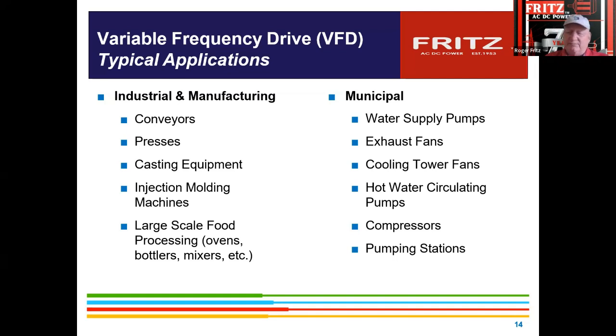We did some processing machines where we put about 60 or 70 drives on molding machines for an optical lens company. And we were able to take 300 tons of chiller off the roof, which they were using to cool the hydraulic oil chillers and also cool down the building.